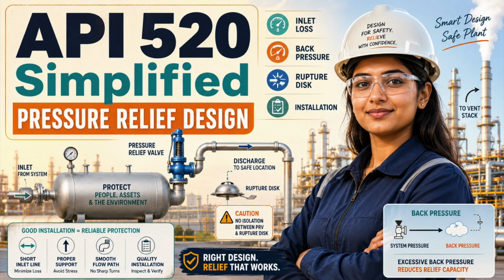Balanced bellows valves are used when back pressure could significantly influence a conventional valve. The bellows arrangement reduces the effect of outlet pressure on the moving assembly and can also help isolate internal components from corrosive service. But the bonnet vent is part of the functional design. If that vent is blocked, plugged, pressurized, or routed into an unsuitable system, the balancing function can be compromised. A balanced valve with a badly engineered bonnet vent is not a balanced installation.